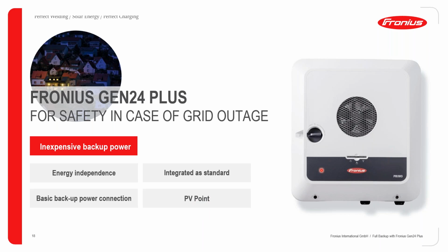Okay, so the PV Point is a separate outlet on the inverter. So you don't need any DC disconnection boxes for the PV Point, or any grid separation boxes. The reason for this, as I said, is that the PV Point has a separate outlet on the inverter. So when the grid goes down, the separate outlet on the inverter gets activated, and you will then get 3 kilowatts single phase being sent to this single output. Only if you have enough irradiation coming from the sun.